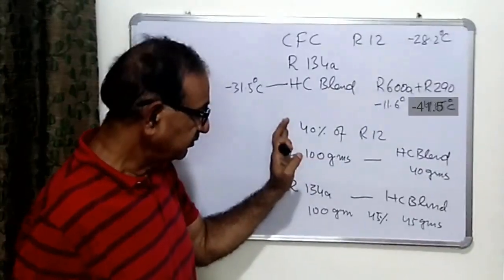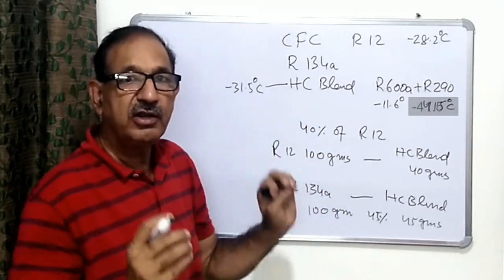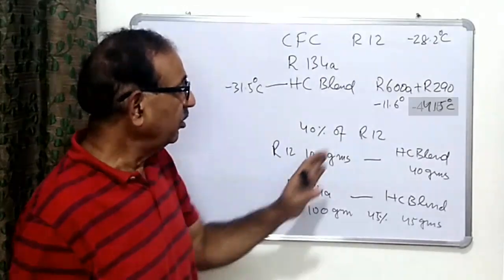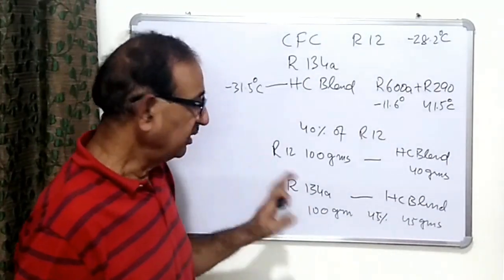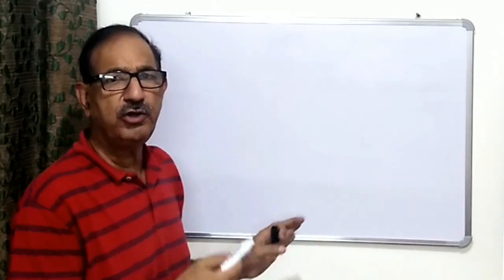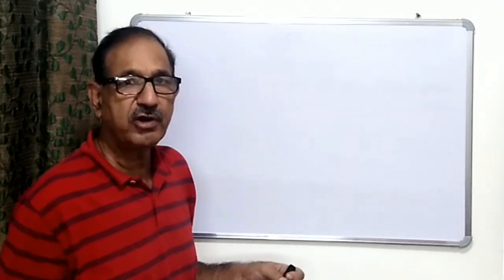This hydrocarbon blend is a mixture of two gases — it is a zeotropic refrigerant — and we have to charge it in liquid condition by keeping the can upside down, because both refrigerants have different boiling temperatures. Take care while charging this hydrocarbon blend in the refrigerator. The hydrocarbon blend is compatible with both POE oil and mineral oil, so there is no need to replace the compressor oil.